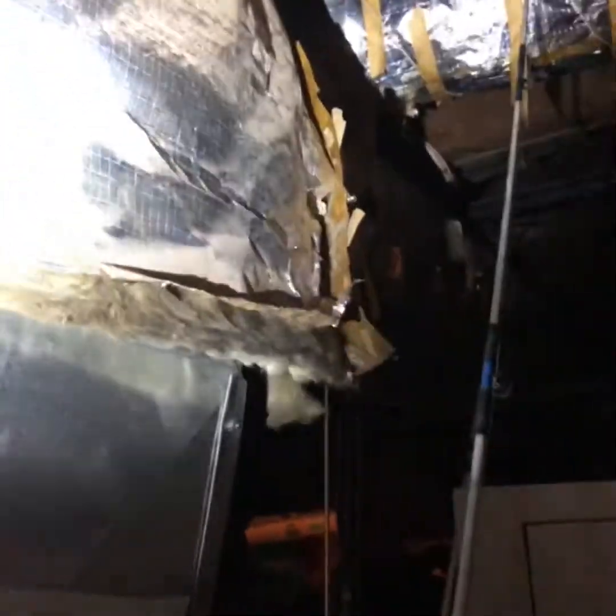From here at the furnace - there is no service on the upper level of this home - so we'll end up putting in ductwork, running it through the house up to the attic, and distributing from there. Right here on the plenum we'll grab a 12-inch pipe, and we want to run rigid duct. It will come up right about there, fitted between the floor joists so we're not causing structural issues. We'll run it up into the main area, then upstairs into a closet, and from the closet up into the attic to distribute from there.